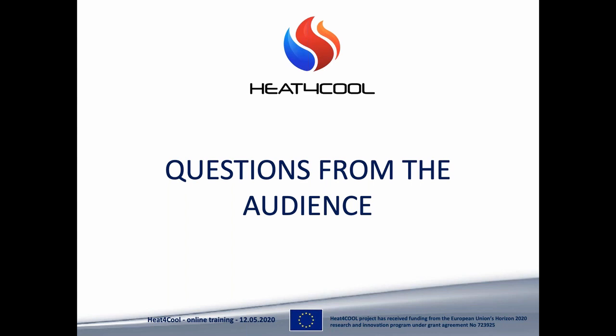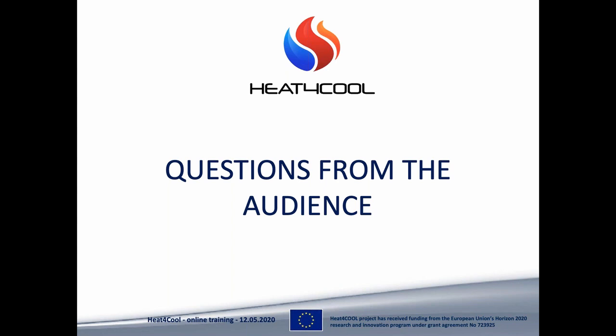First of all, our heat pumps use waste heat - it can be waste heat, solar heat, or heat from processes. So it increases overall energy efficiency. It also consumes up to 90% less electrical energy because it has no compressor. In our machine, the only consumers of electrical energy are water pumps, which usually consume less energy than compressors. We also have a controller, but its energy consumption is marginal.